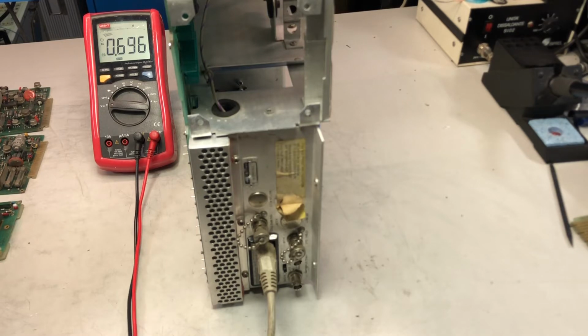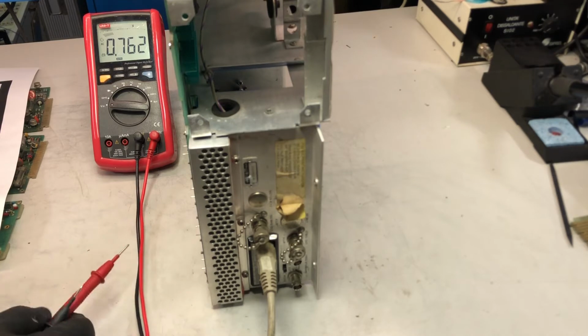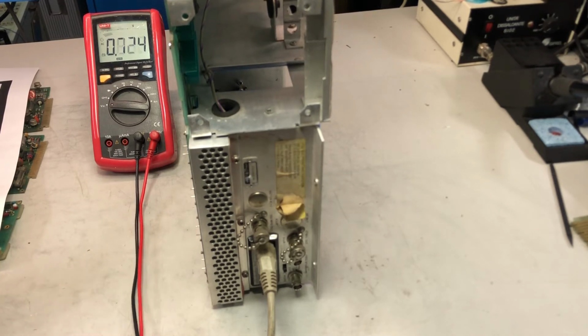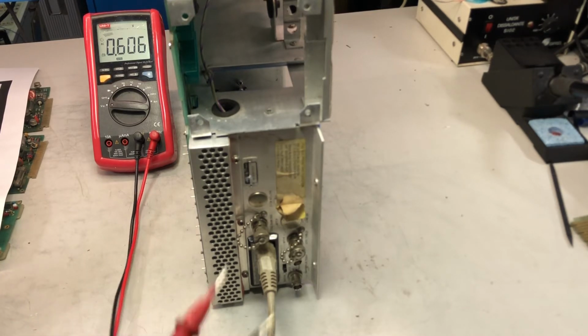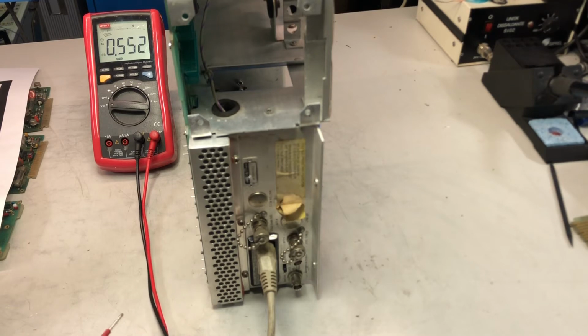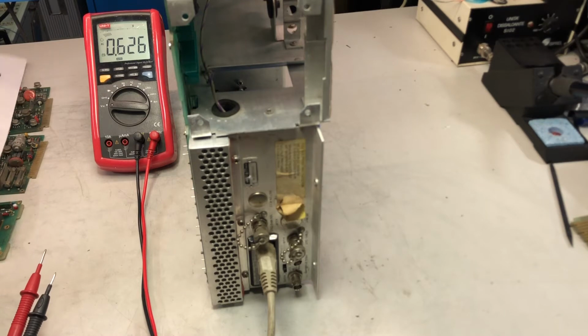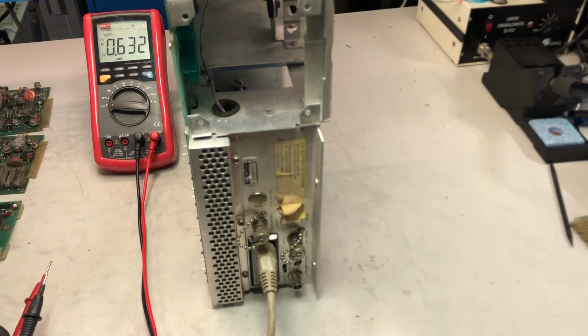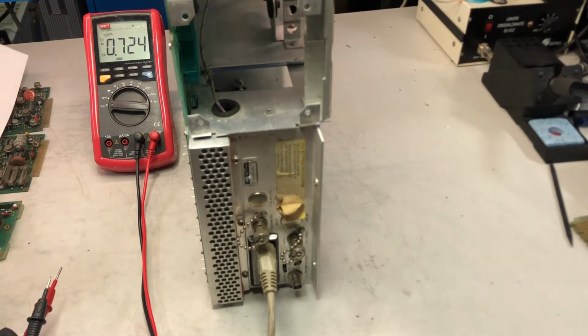So let's go and check the output voltages on the secondary sides of the transformer. Remember that this instrument is set at 220 volts. So since I'm at 50 volts, I should be about 1/3 of the expected voltage.